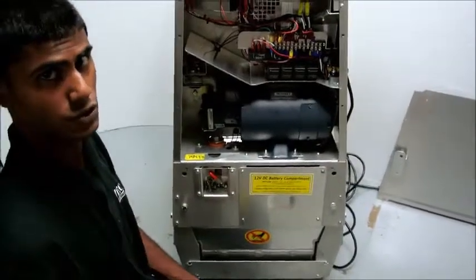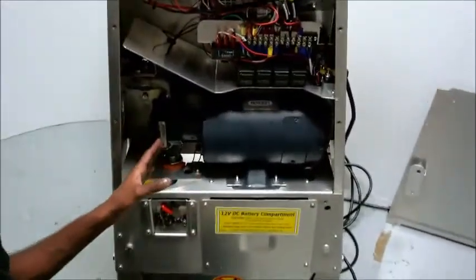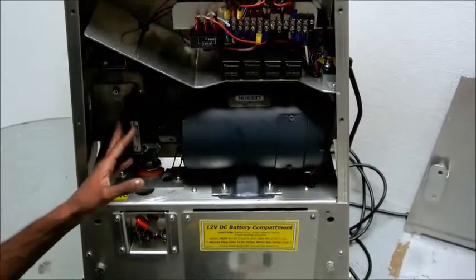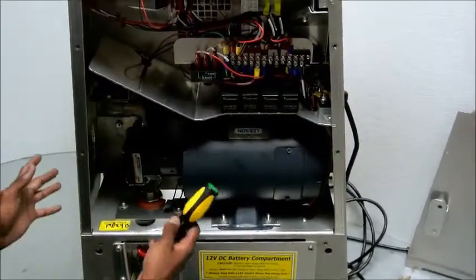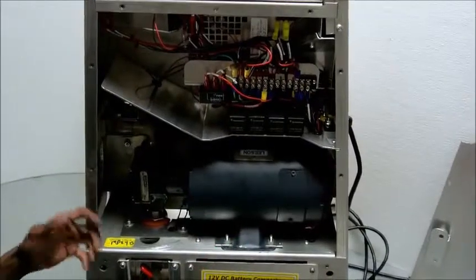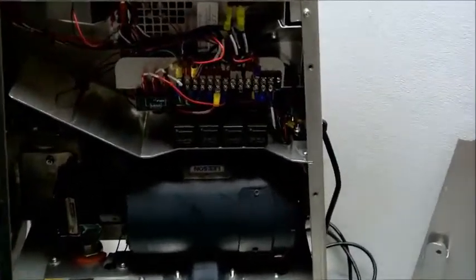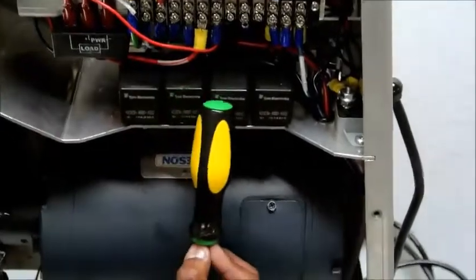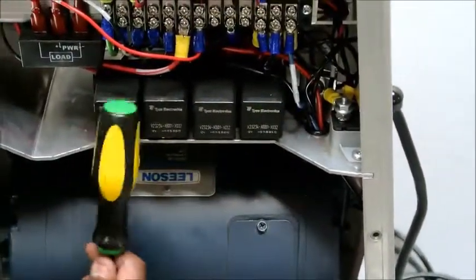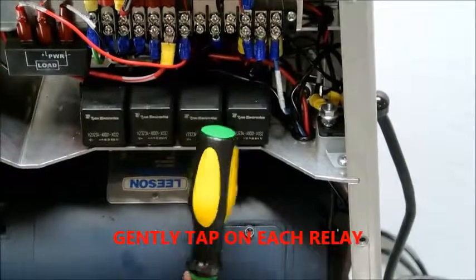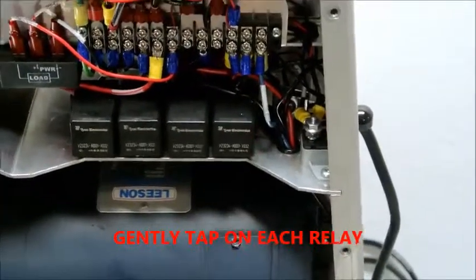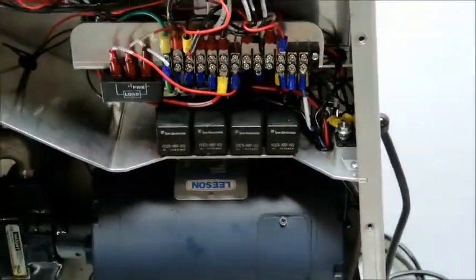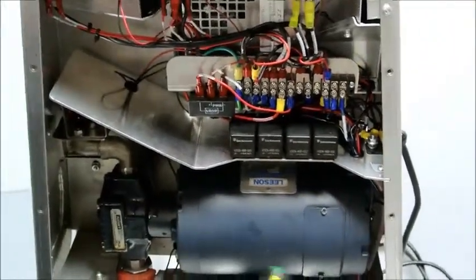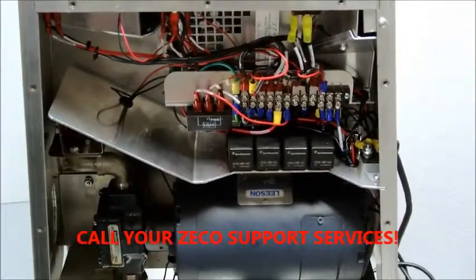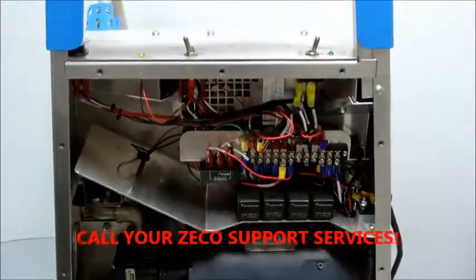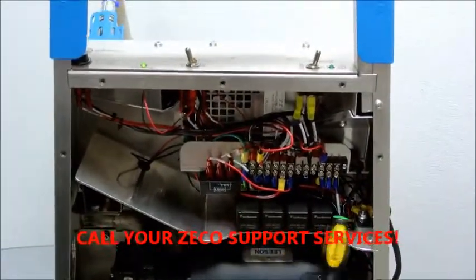If your oil filtration machine runs normally after you have cleaned out the pump, take the back panel, place it on the back, re-screw it in, and use as normal. If not, locate your 4 individual relays and gently tap on each one of those. If it works, continue as used. But if not, call your oil technician right away to help repair the machine.